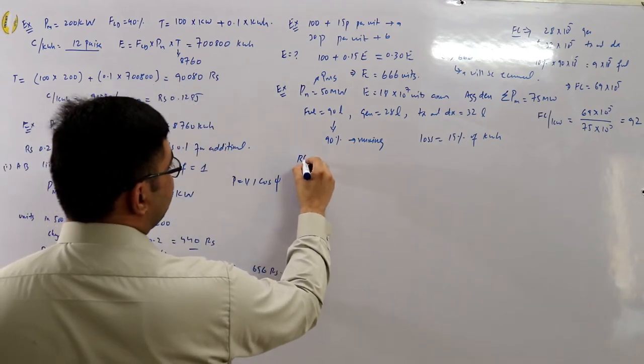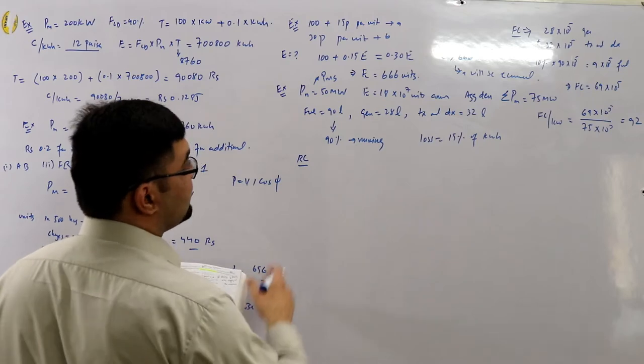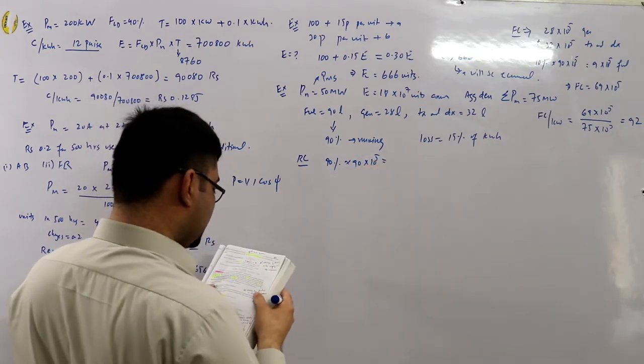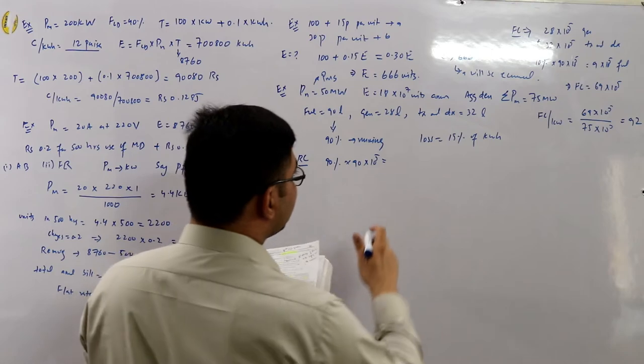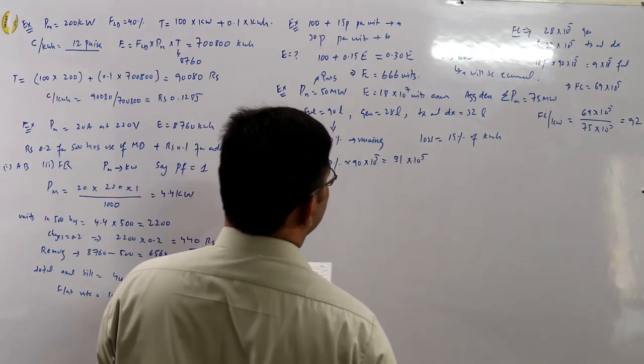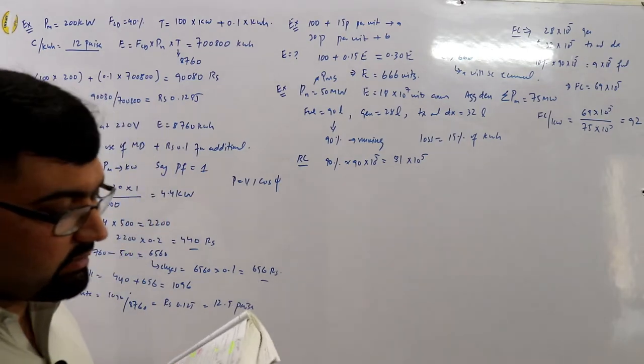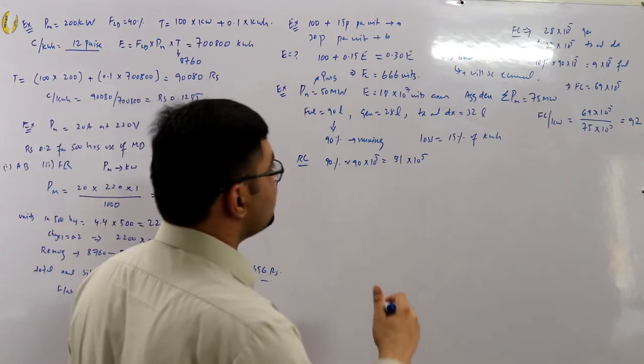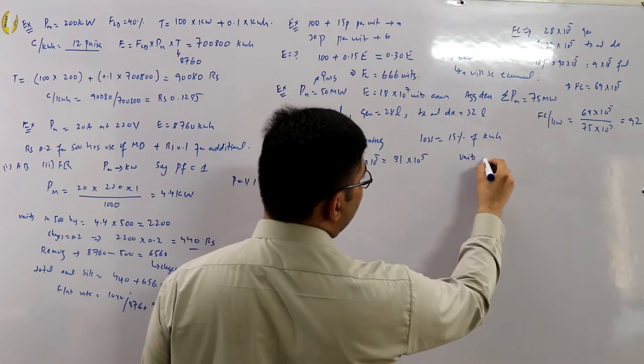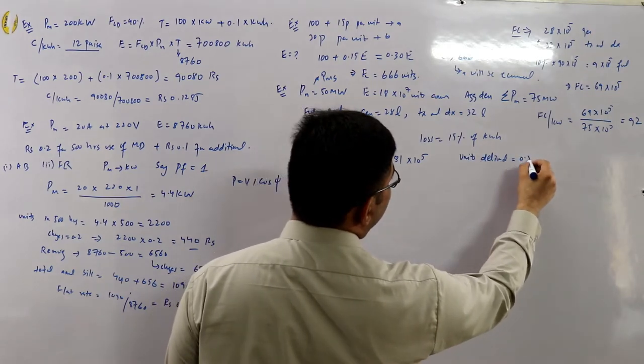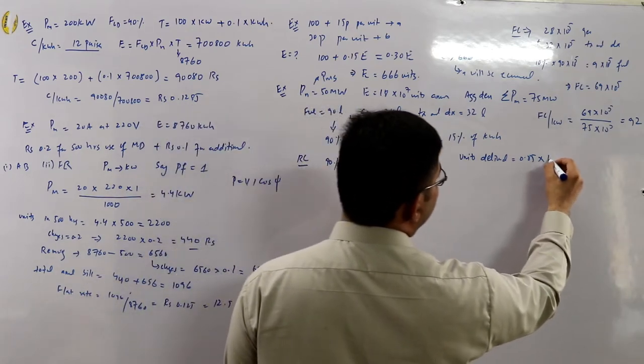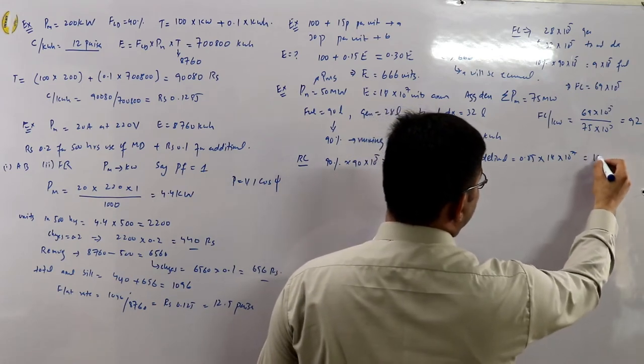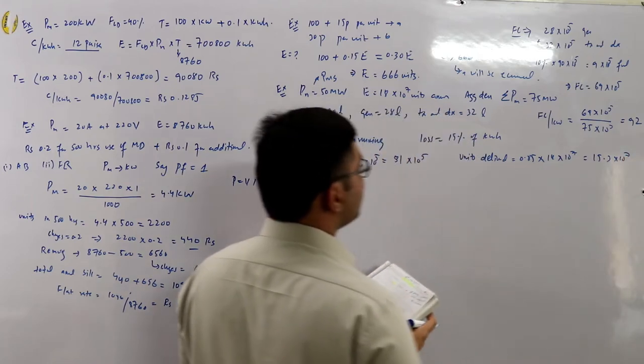Running charges: 90 percent of fuel = 81 × 10⁵ rupees. Units delivered are 85 percent of units generated: 0.85 × 18 × 10⁷ = 15.3 × 10⁷ units. These are the units actually delivered to consumers.